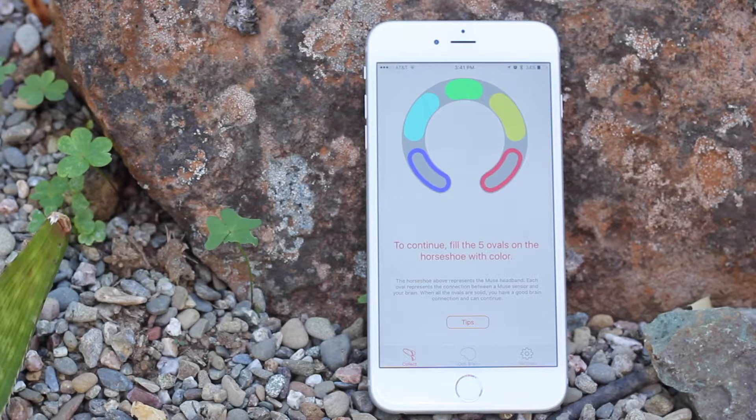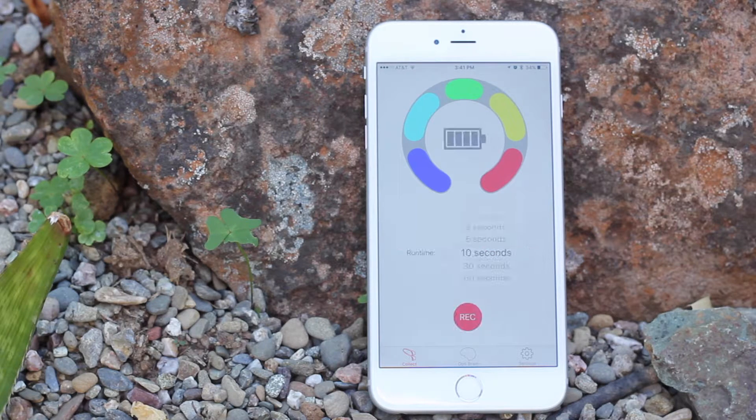What I'm typically going to do is turn on OptiBrain and go to collect mode. You'll see the signals start coming in. Each of these different colors represents one of the different electrodes, and we'll do some adjustments here. As those all get filled in, we know everything is connected and we're going to get good signals.